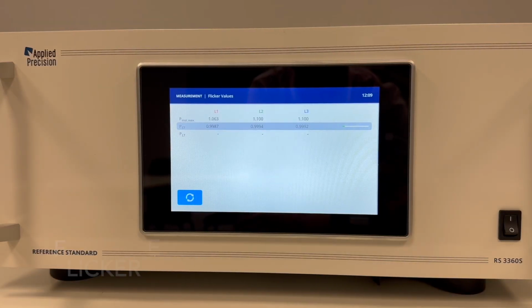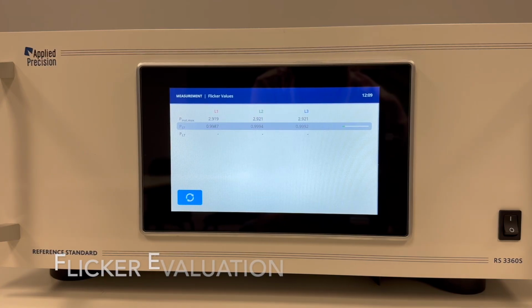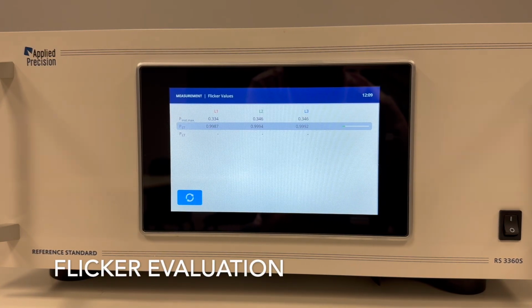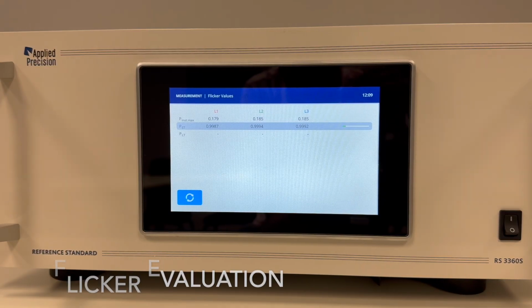And finally, we can return to the flicker measurement, which is already done, so we can see the value of PST. Now here it's less than 1, it's 0.99, which is what we really expect, slightly below 1, so it's okay right now. We have the value of the flicker in all 3 phases.